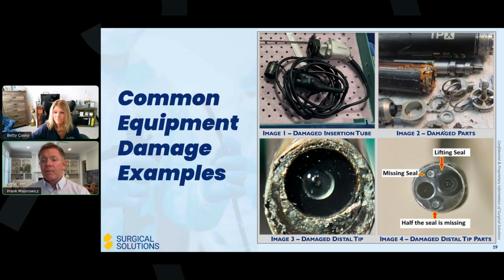And then image number 4, that's the distal tip of a flexible endoscope. And it's just pointing to some common issues that we see at the tip of a flexible scope. In the previous slide, I referenced glass lenses at the tip. You can see the lenses there. There's 3 of them. You can see the opening of the biopsy port, which is on the left-hand side of that image.